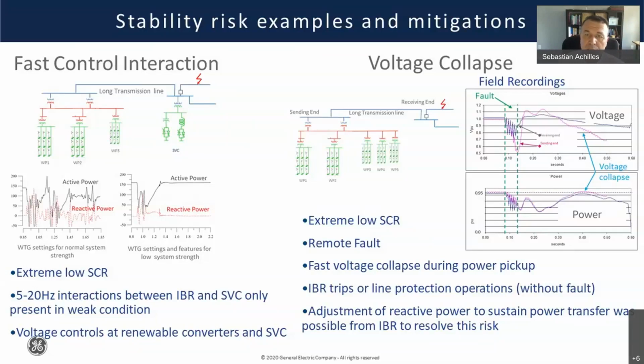The case on the right is a voltage collapse. But voltage collapse, IBR flavor, is quite different from the voltage collapse that the industry has talked about for so many years related to load behavior. So this case is not too different from the other one, although the characteristic voltage levels were different, but fundamentally you have a very large group of wind plants that are connected through a long transmission line, as shown in the diagram in the upper center of the slide. In this case, we also have a remote fault that is cleared, and what you see on the right are actually field recordings of this event that happened many years ago.